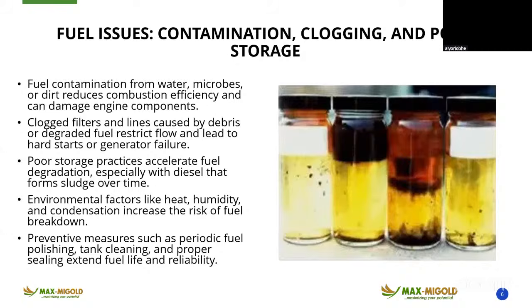We have clogged filters and lines caused by debris or degraded fuel. Contaminated water makes your fuel filter clog. I ran a facility where every 5 days they were changing the fuel filter, until I presented to management to do a thorough cleaning of their underground storage tank, which they did. At the end of the day, the fuel was clean and they no longer had to change the filter as often. These are things to pay attention to when managing your generator - water in diesel will make your filter choke and clog, causing unexpected generator shutdown. Poor storage practice also accelerates fuel degradation, especially with diesel, which forms sludge over time.